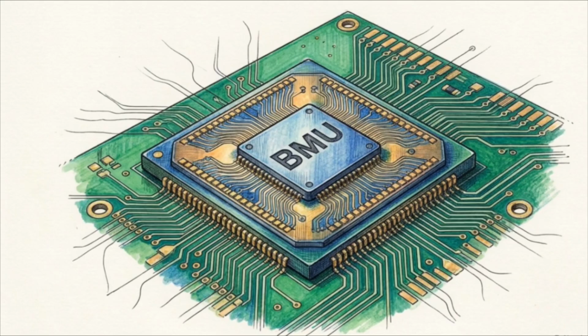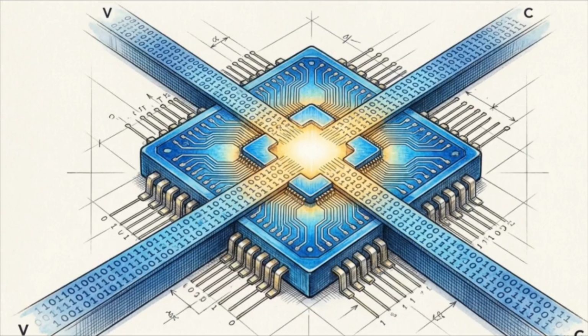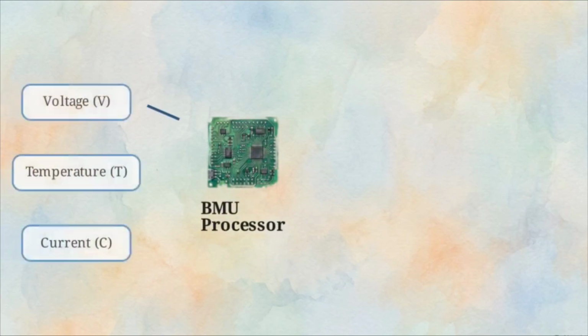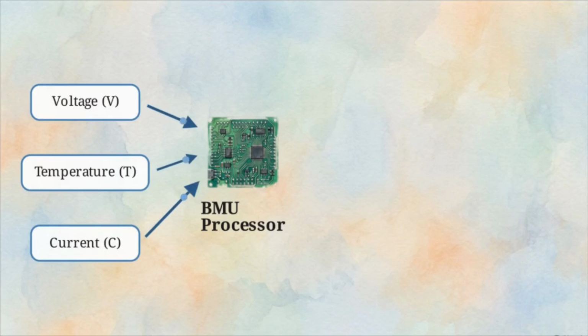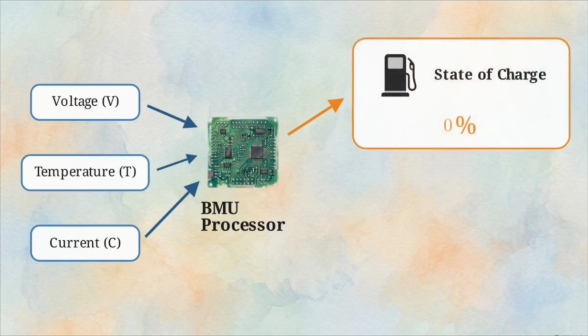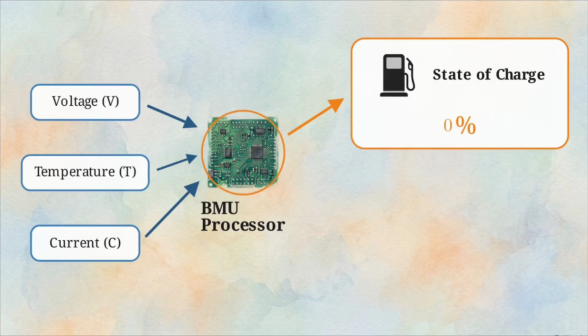requires processing to be useful, which is handled by the third and central module, the Battery Management Unit, or BMU. The BMU acts as the brain of the architecture, running complex algorithms to contextualize the incoming voltage, temperature, and current readings. This block diagram maps how those inputs flow into the processor. The first critical algorithmic output is the state of charge. Total remaining energy cannot be directly measured by any physical sensor. Instead, the BMU algorithmically estimates state of charge, functioning as the system's fuel gauge.